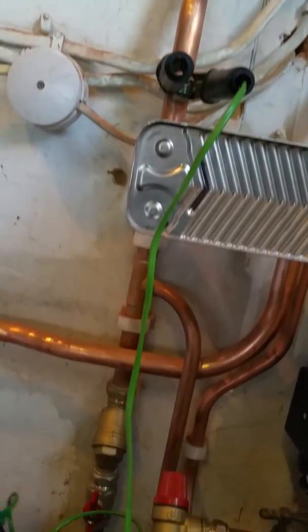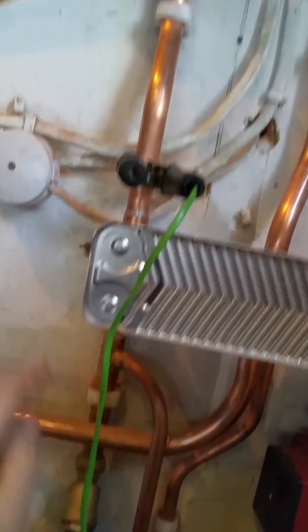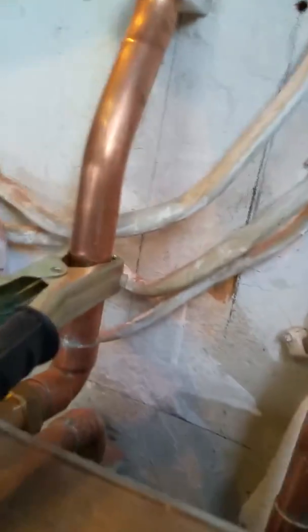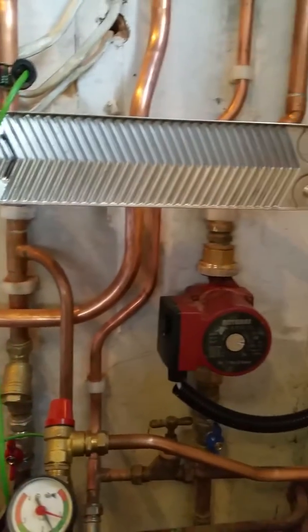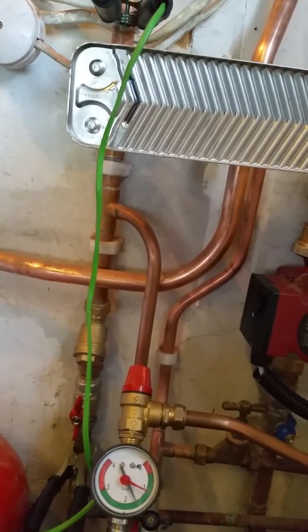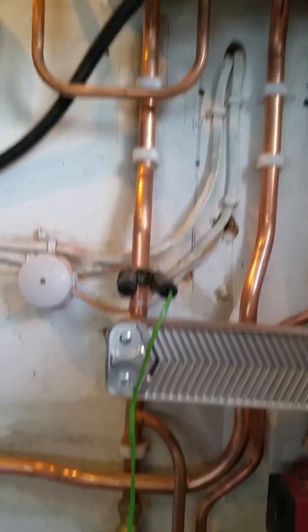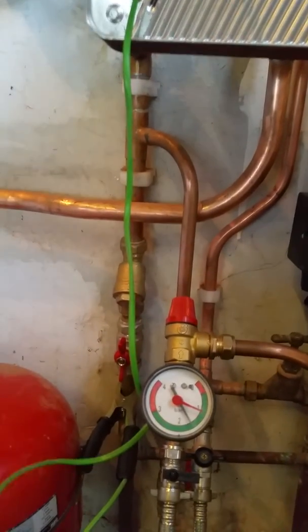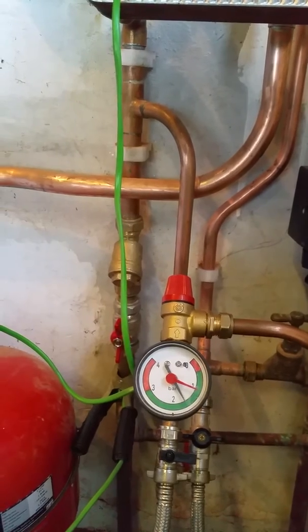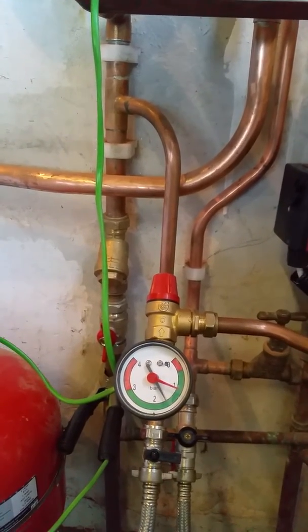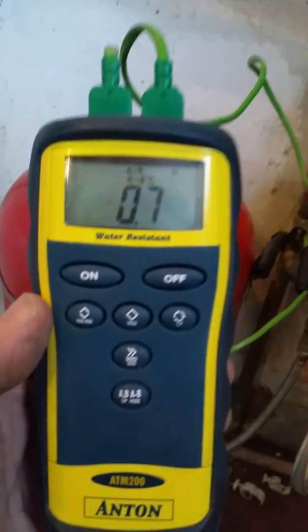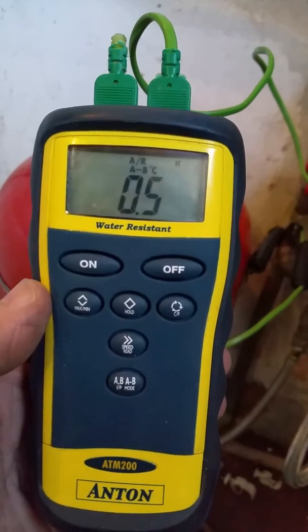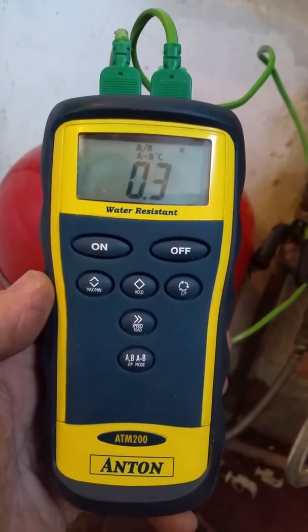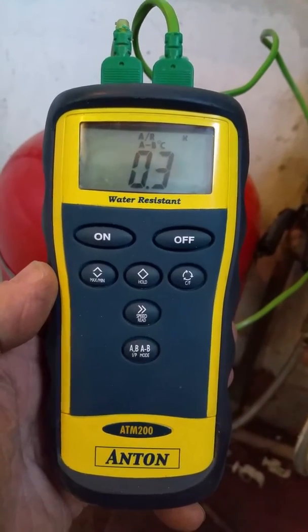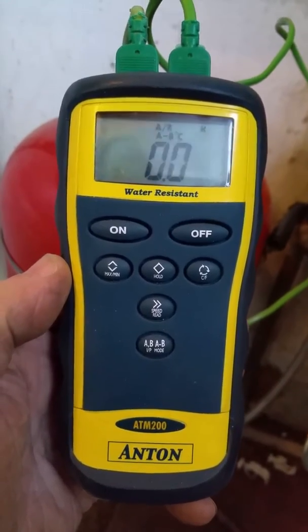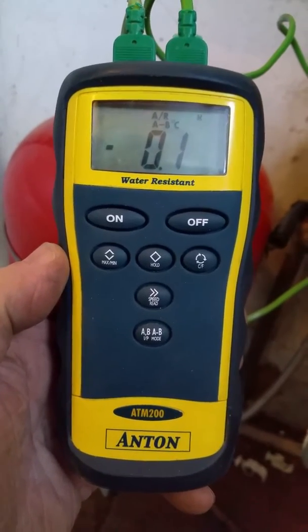What we want is as close a match between the flow on the boiler and the flow on the secondary side. Now the closer they are, the less extra temperature required to come from the boiler to get our correct temperature in the radiators. So we really want something nice and low, and I've been measuring this for a little while, and I've been getting 0.5, and that's actually the wrong side at the moment. The sensor's just settling in, so that's giving me a positive reading, but the leads are connected the wrong way around, so I need a negative reading, and I'm looking for a negative of 0.5 degrees C, which is what I've been getting most of the time.